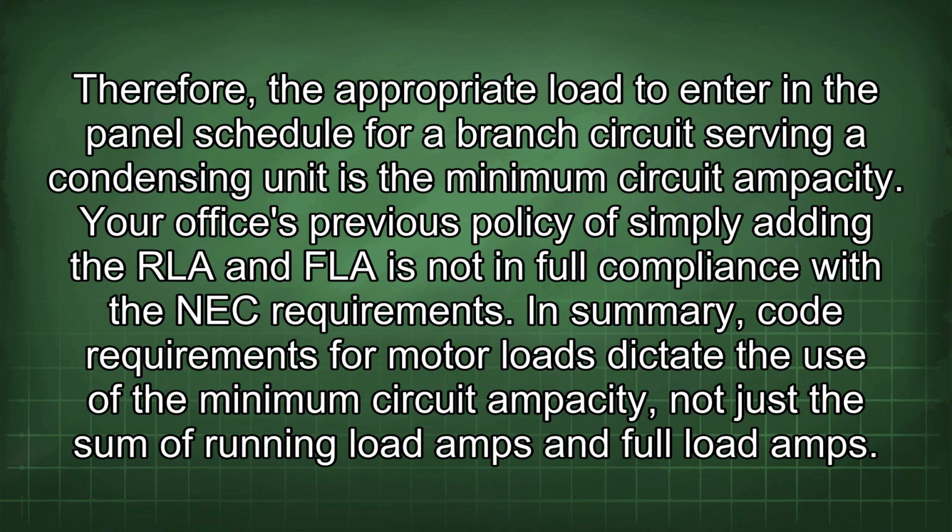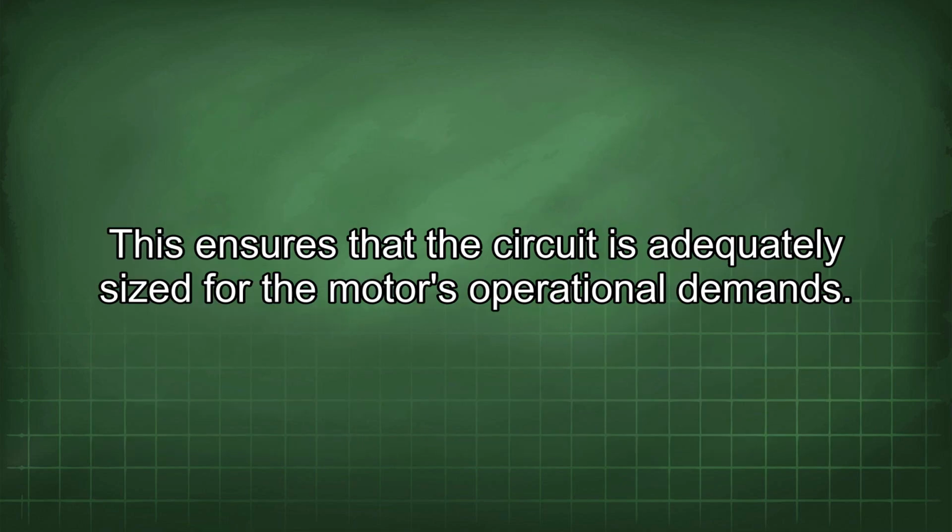the NEC requirements. In summary, code requirements for motor loads dictate the use of the minimum circuit ampacity, not just the sum of running load amps and full load amps. This ensures that the circuit is adequately sized for the motor's operational demands.